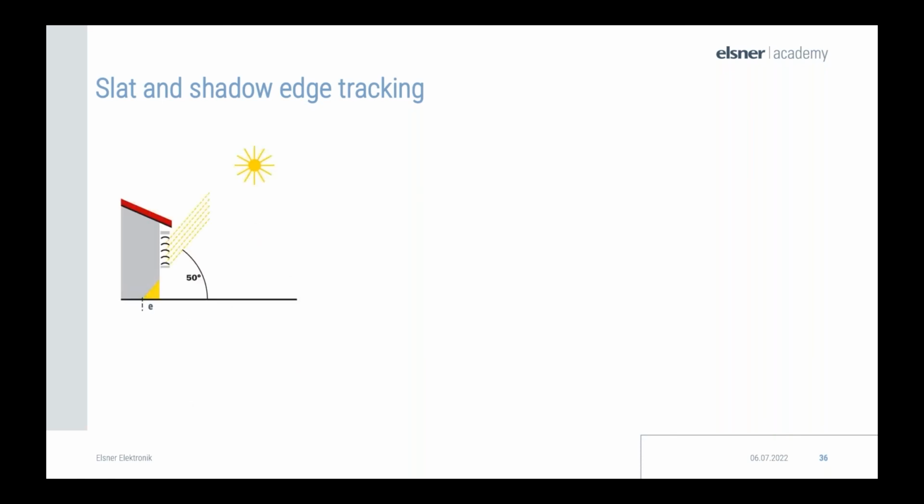Here we have some visualizations for what we just discussed. So the sunshade for high sun: the sunshade is only partially closed and automatically lowered, only so far that the sun cannot shine further into the room than the maximum permitted penetration depth specified above.